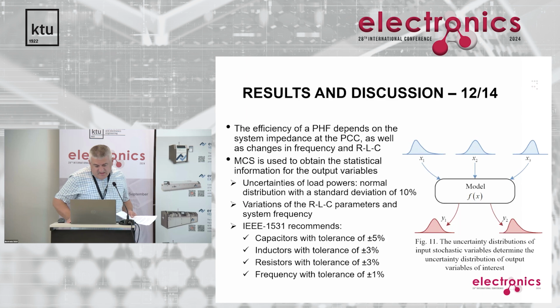What is interesting here is that the efficiency of a passive harmonic filter depends on the system impedance at the PCC, as well as changes in frequency and RLC load. This algorithm is used to obtain the statistical information for the output variables.